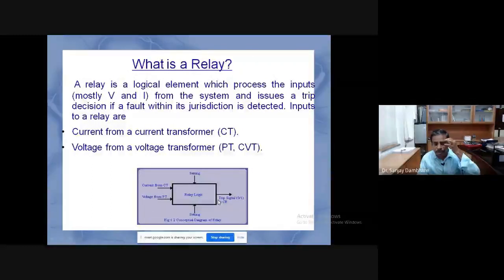Now, talking of protection, there is no change in the basic protection philosophy, but what has changed over the years is the technology used for the relay. Earlier these were electromechanical kind of relays, since we were all working with electromechanical technology. Then we had solid state relays, as solid state technology became important.